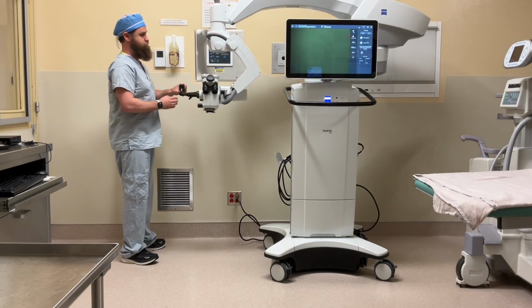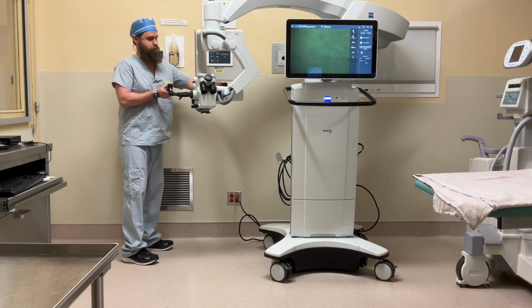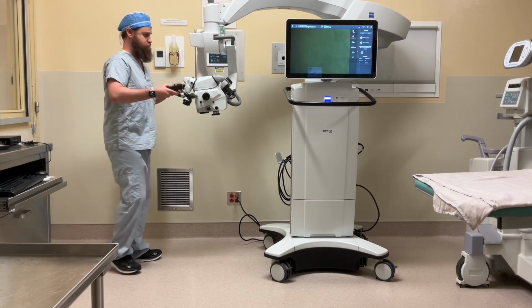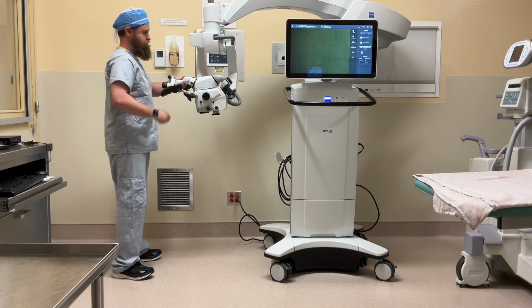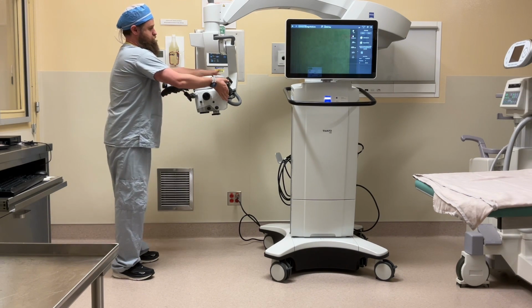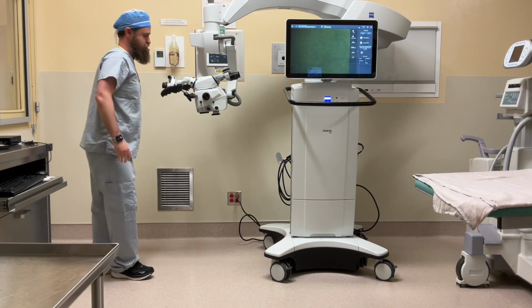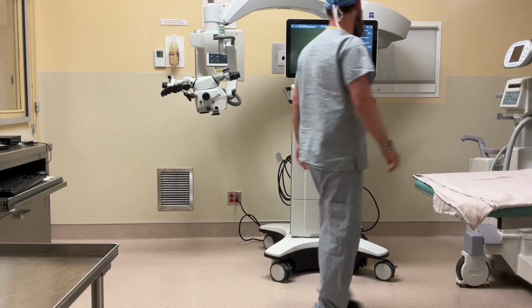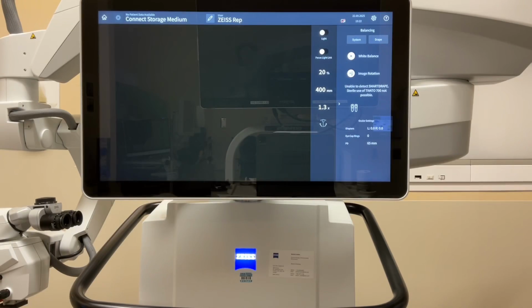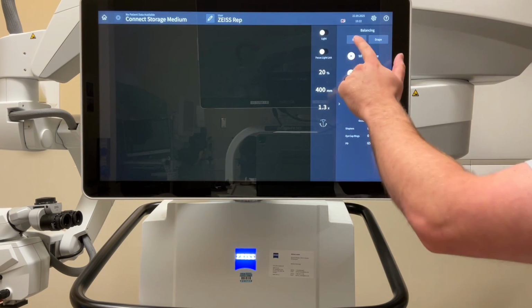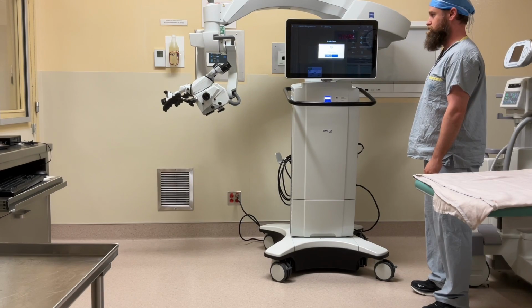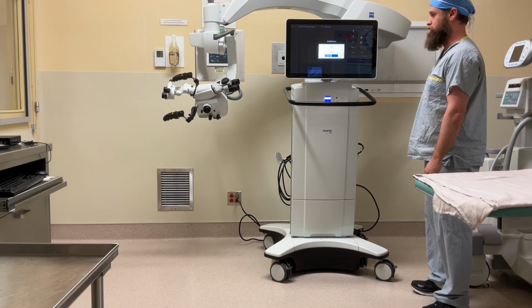The microscope needs to be balanced when first turned on. To do this, release the brakes by pushing the bottom green button on the hand grip to move it away from the stand. Put the binoculars in the surgical position. On the home screen, under Balancing, push System. Ensure this is not being done over a patient. The system will automatically balance itself. This takes approximately 15 seconds.